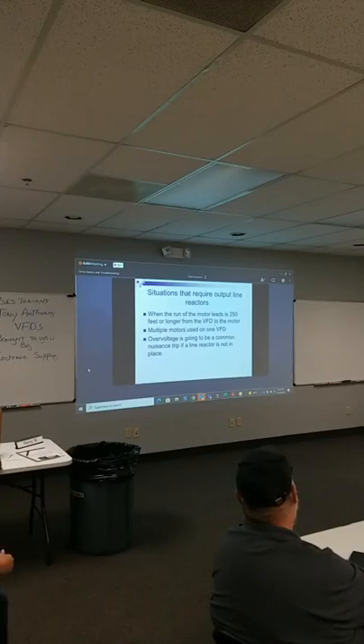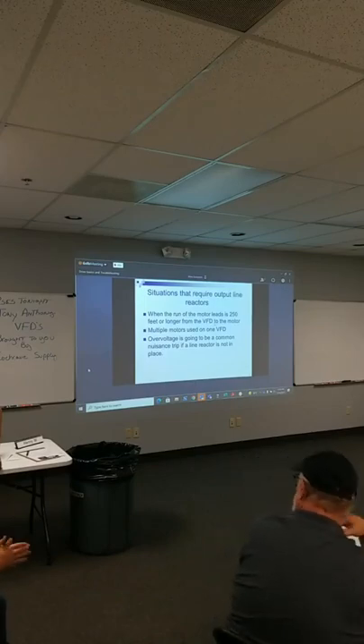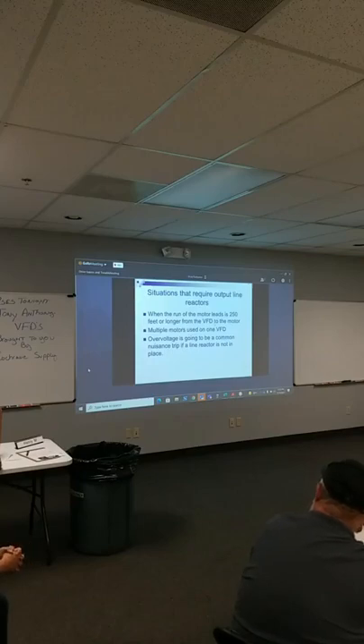But another time you may need protection, even if it's only 40 foot away, a lot of people don't realize this, you can actually run like 3 or 4 motors. You may have seen this on fan arrays, where you may have 4 or 5 motors on one drive. Think about those motors, they're all going to run the same speed. And you don't want to shut one off and bring it back on when the drive's running. So they all have to shut off and on at the same time. But you also need to provide overload protection for each individual motor. Let's say you've got 5 10-horse motors on a 60 horse drive. So that drive sees just a big 50 horsepower motor. If one of those motors starts to overload, we'll never know it because the others are fine. So you have to provide individual protection for the motors.